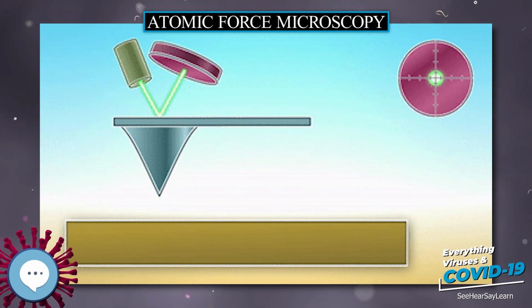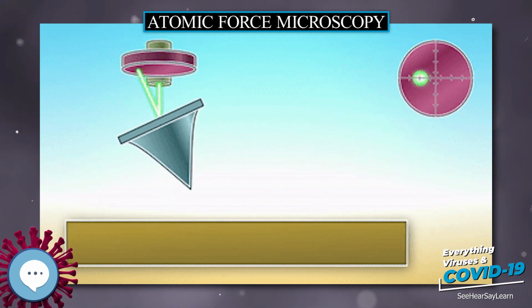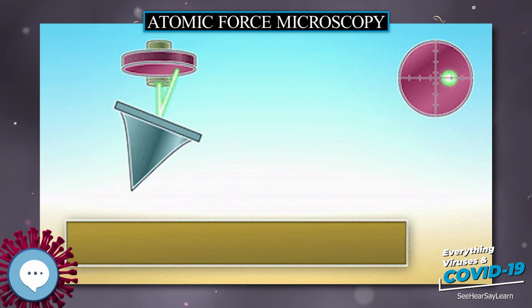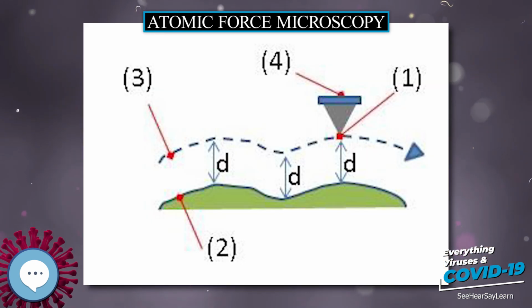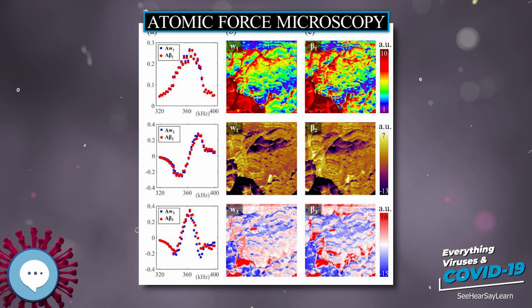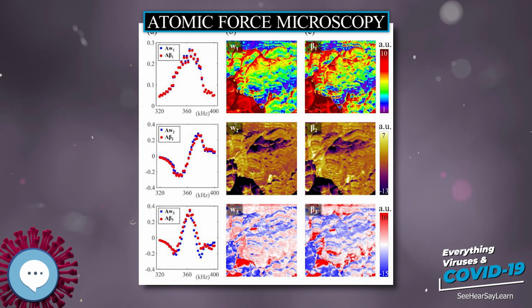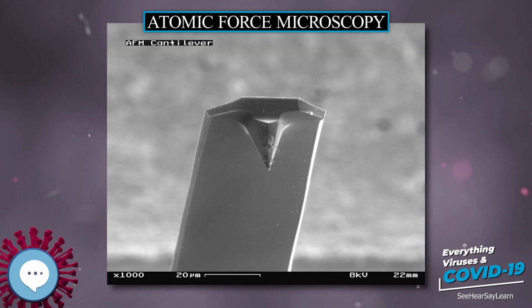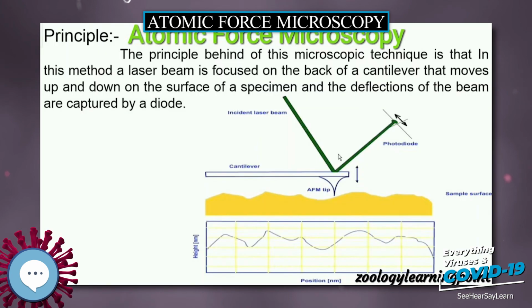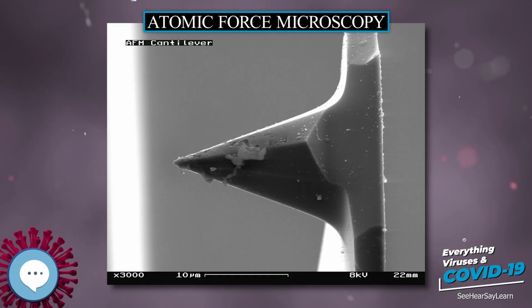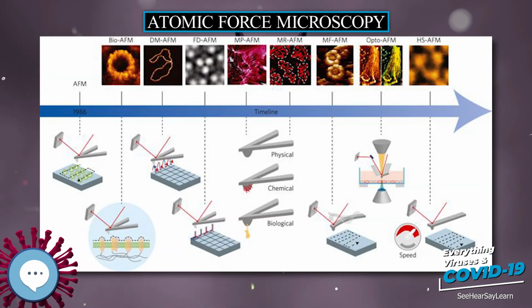Topographic image. Image formation is a plotting method that produces a color mapping through changing the XY position of the tip while scanning and recording the measured variable, i.e. the intensity of control signal, to each XY coordinate. The color mapping shows the measured value corresponding to each coordinate. The image expresses the intensity of a value as a hue. Usually, the correspondence between the intensity of a value and a hue is shown as a color scale in the explanatory notes accompanying the image. What is the topographic image of atomic force microscope?